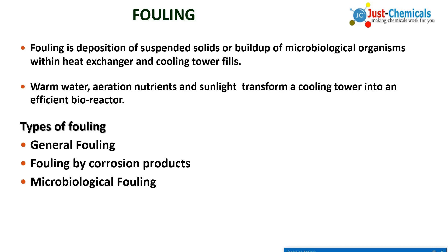And microbiological fouling is like what I've told you, Pseudomonas making biofilm, and that biofilm attracts the suspended solids and fouls the place. Microbiological fouling is the worst fouling I have ever seen in the last 20 years. Microbiological fouling does not have good thermal conductivity, so it is worse than any other kind of scaling. Okay, we'll show you the thermal.